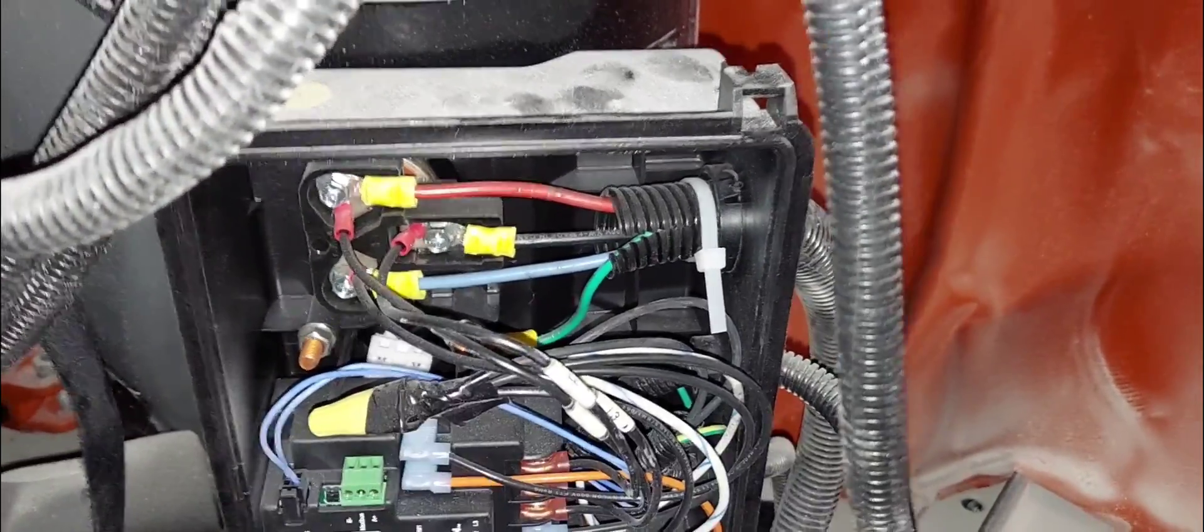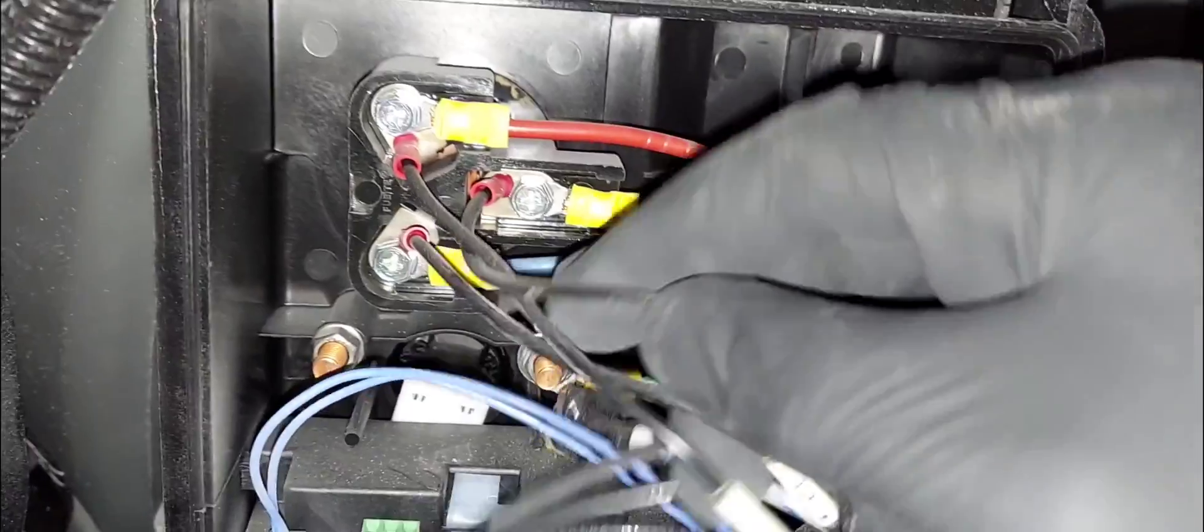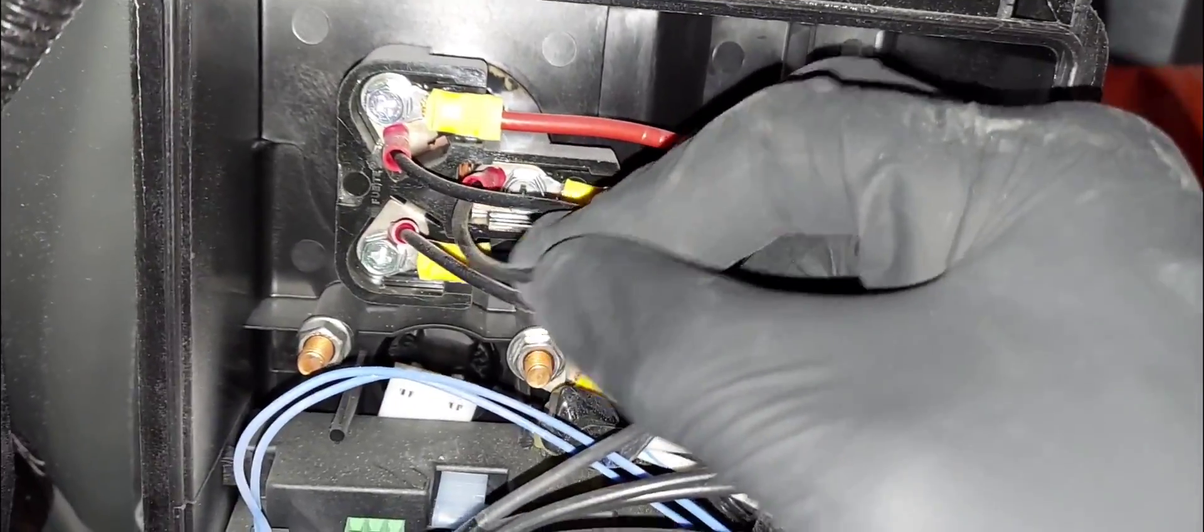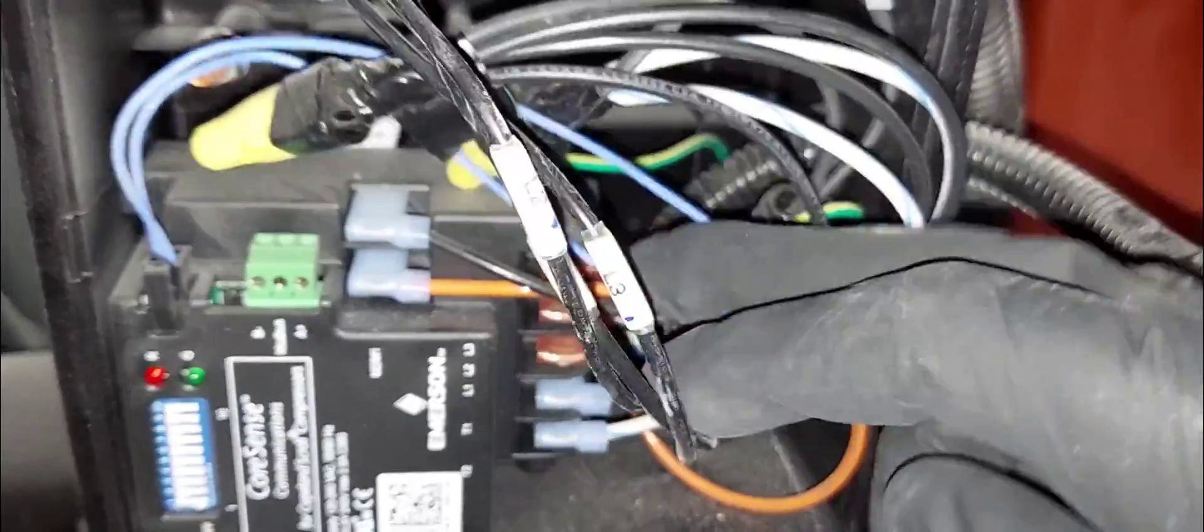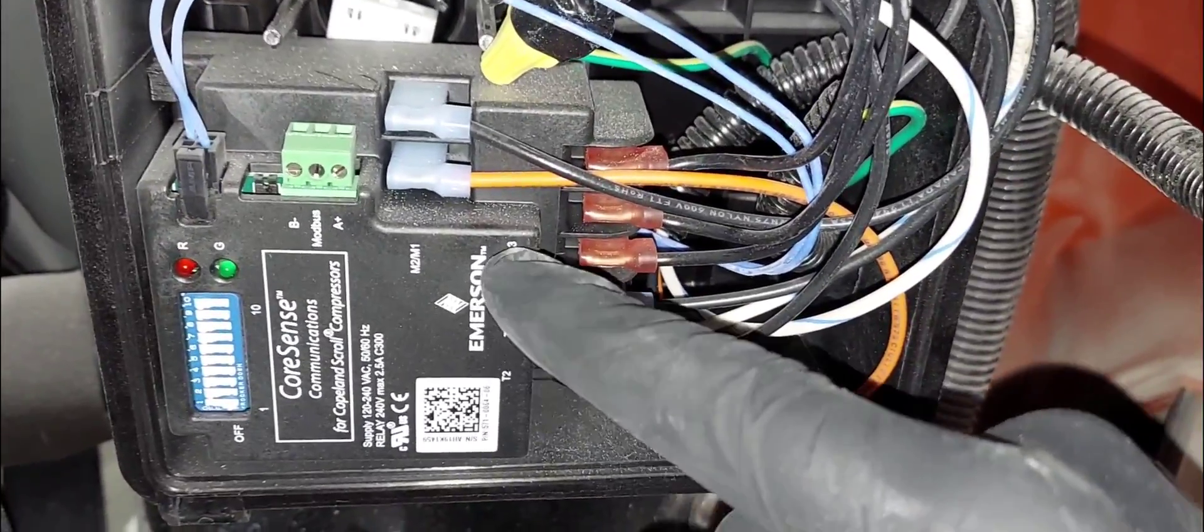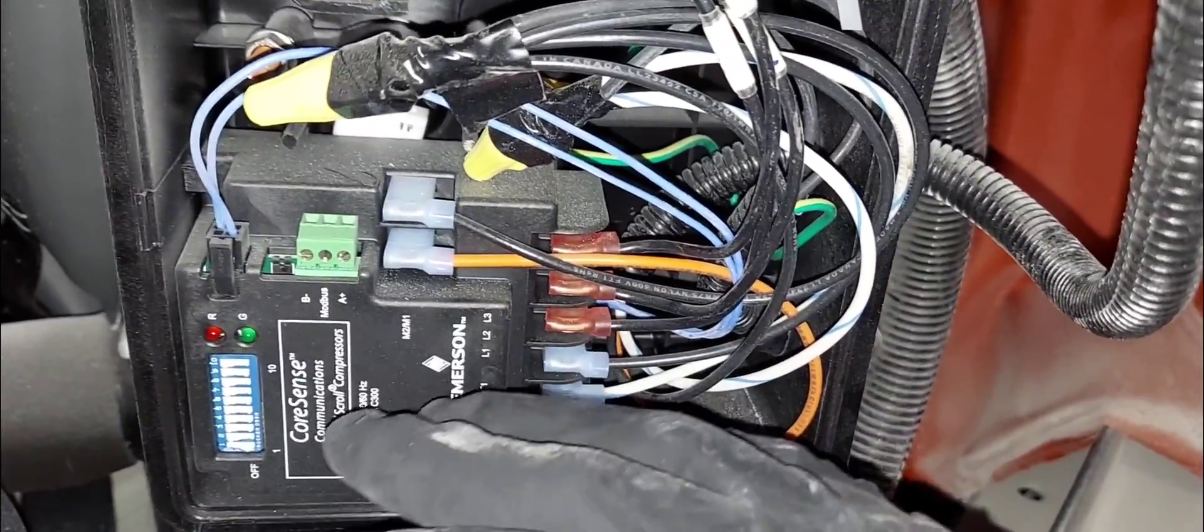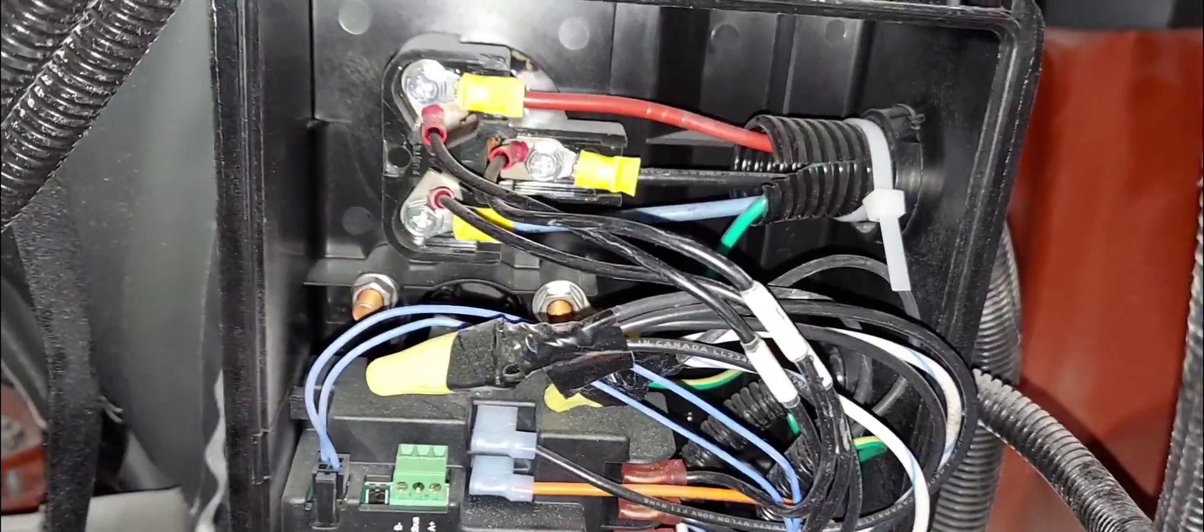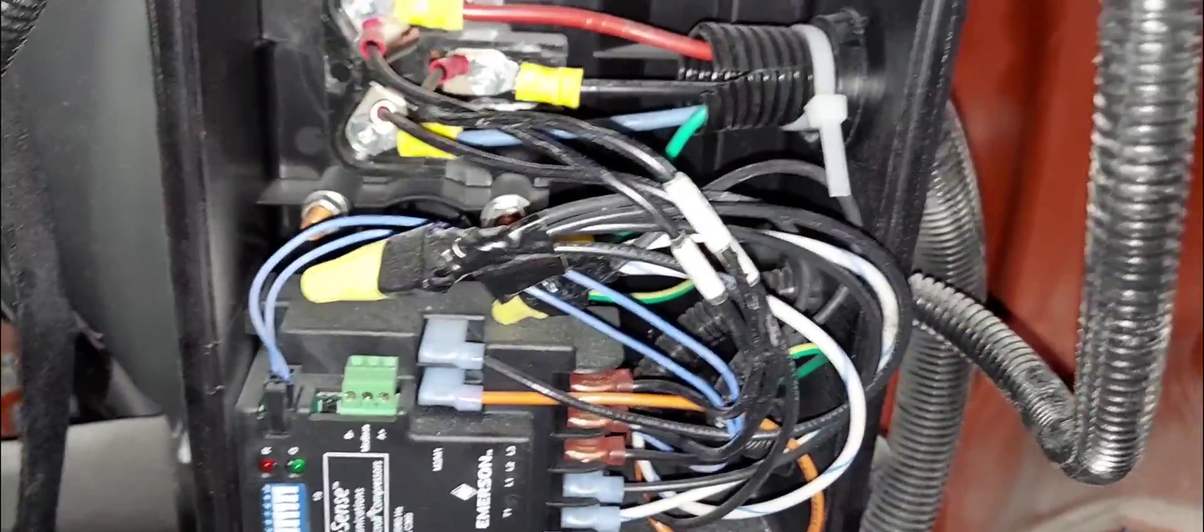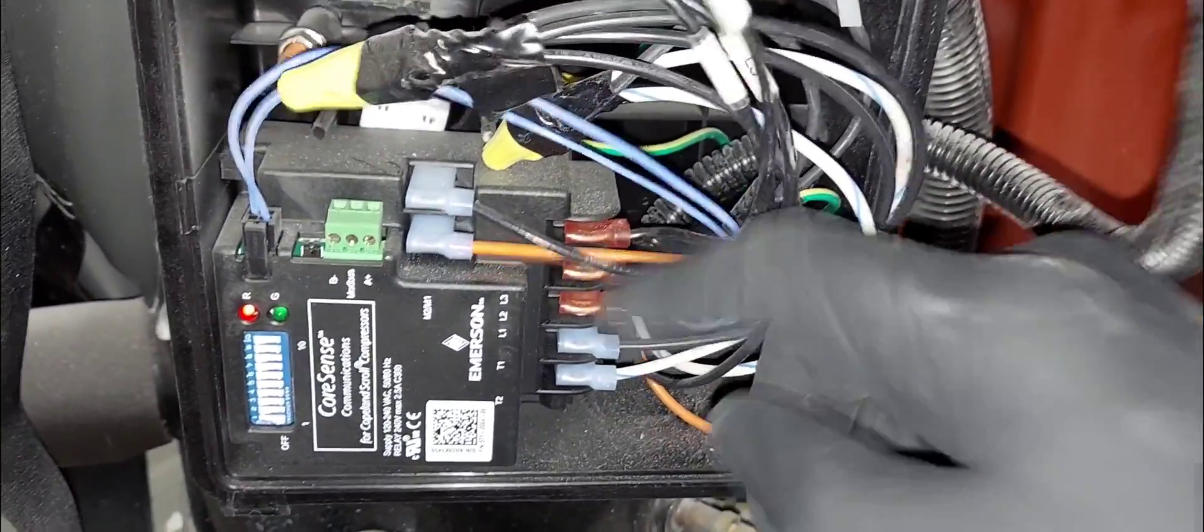Line one, line two, line three - those are good. It just seems like these wires which you can see here, what goes to line one RT1 and line two RT2 and line three RT3, they go back into the phase monitor right here where it says line one, line two, line three. If these are backwards you will get that fault. There's got to be a certain rotation or phase rotation, and if you don't connect these things properly, then it will throw you a fault even though the compressor is rotating the right way.